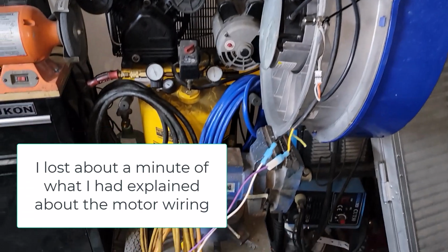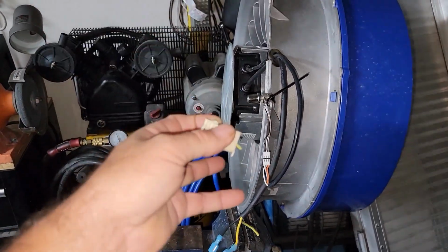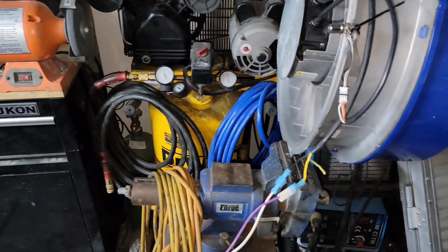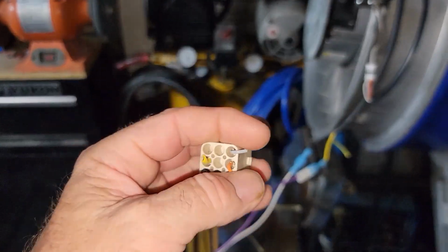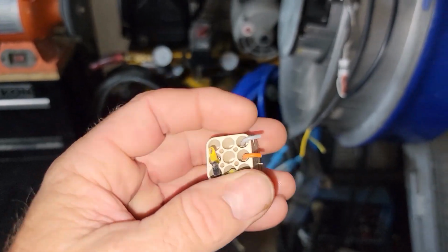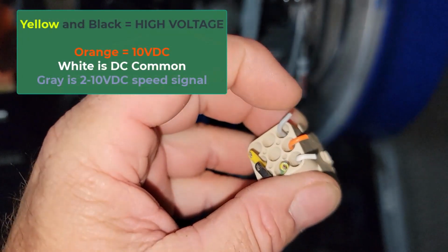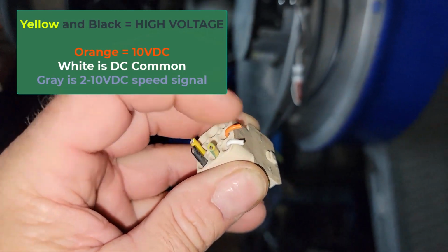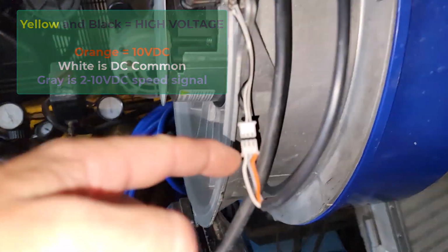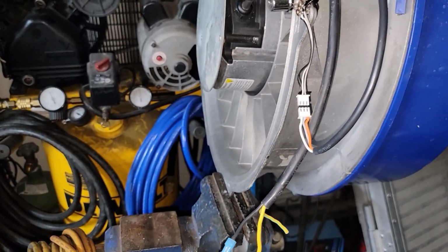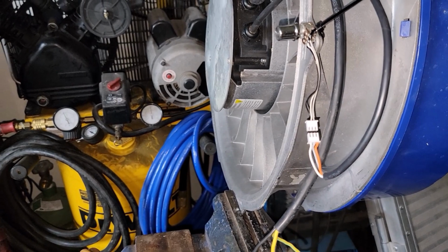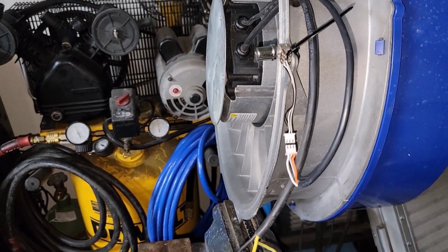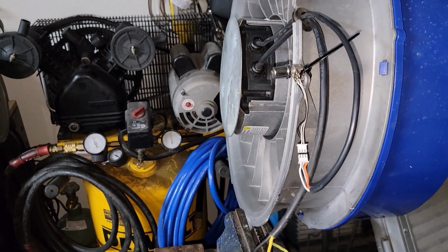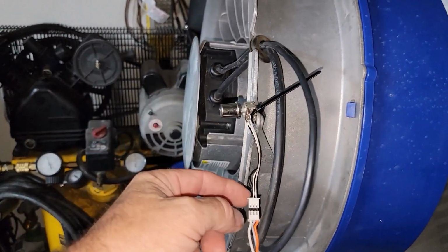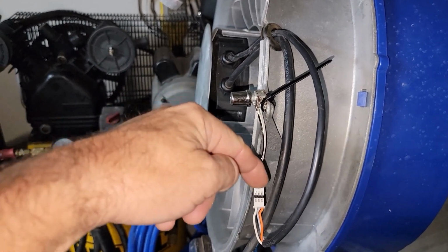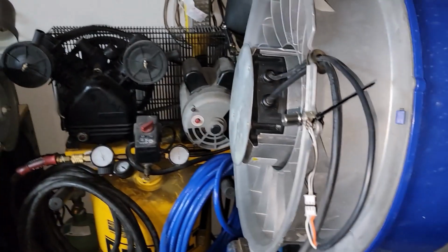So where was I? I was just saying the 10 volts is provided by the motor. If you don't have that, the motor's already bad. If you do have that, then you want to make sure that your control board or whatever you're using to send the speed command is sending voltage to the gray wire, between gray and white. White's always common, and you should have at least 2 volts for it to run. Usually you're probably going to see between 4 and 8 volts on most setup units, but 2 to 10 is the range. So you can just take a potentiometer, negative, plus 10 volts, and from the wiper in the middle you can vary the 2 to 10 going into it. That's all it takes.